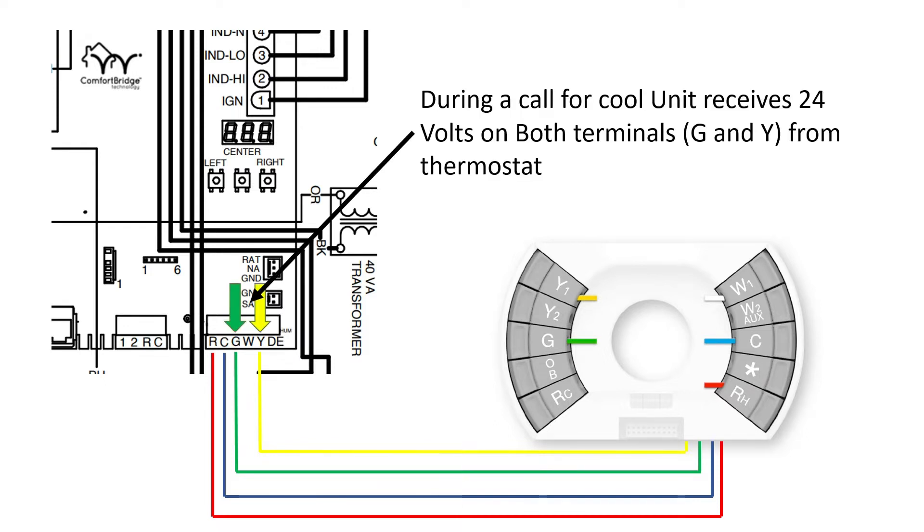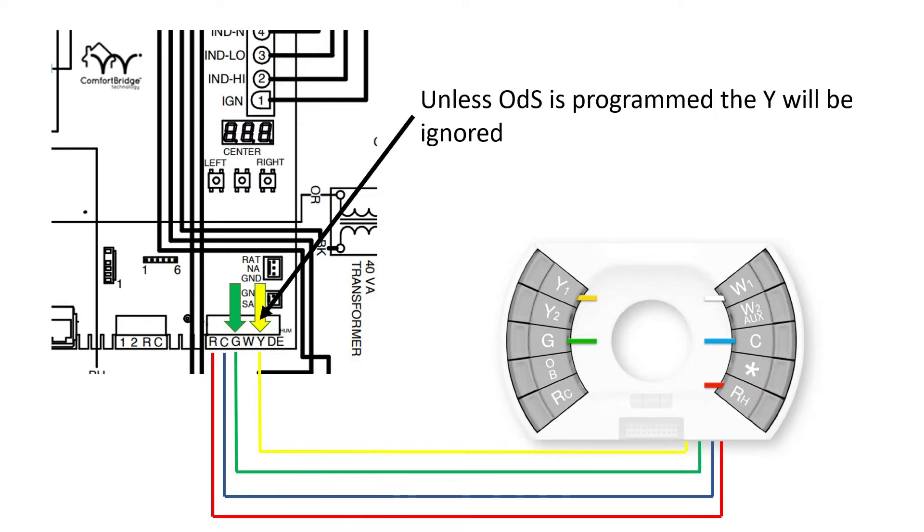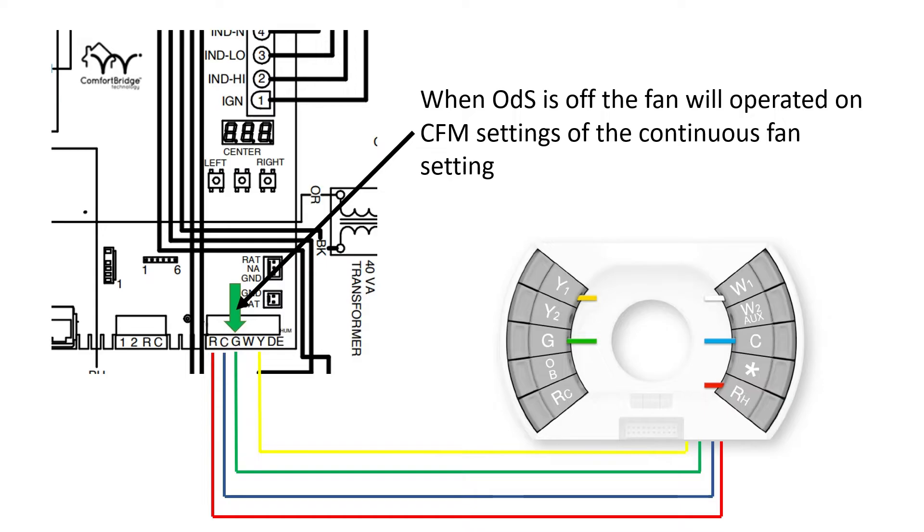But during a call for cool, we're going to energize both the G and the Y from the thermostat. And the Y normally would give us our CFM for our cooling call. But if we don't have it switched on, it's going to be ignored. When it's ignored and you call for cool, we're going to get the fan CFM to come on and we're going to be running short on the CFM.